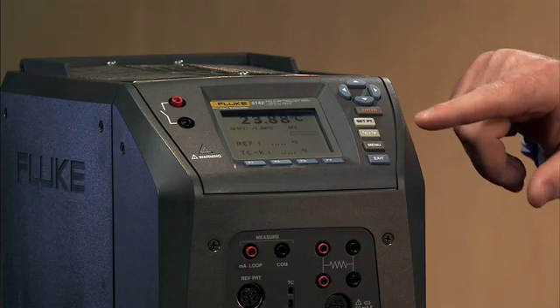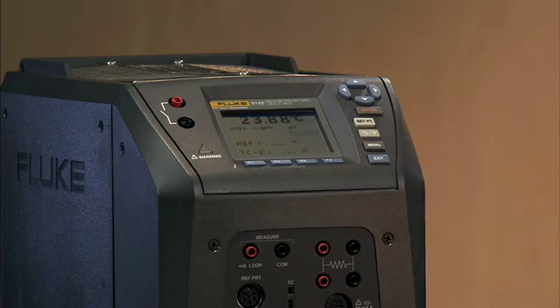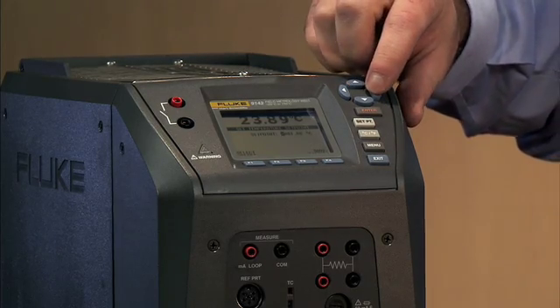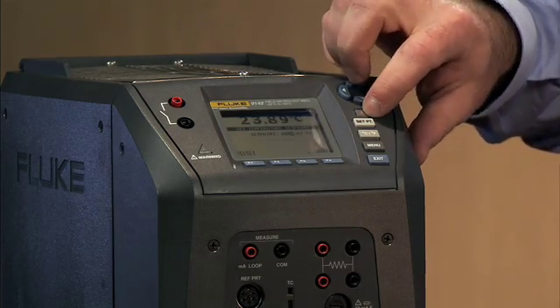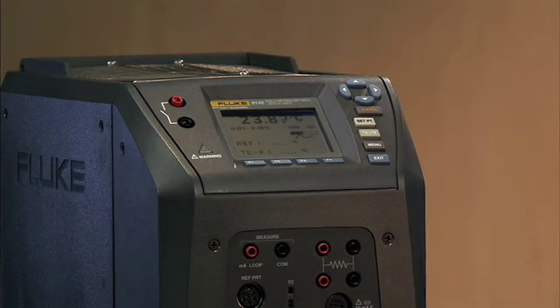As you see on this front panel, we have the set point temperature — we've dedicated a button just to allow you to set the temperature. So you go ahead and press that, press enter, and then you enter the desired temperature that you want. In this case, let's go to zero degrees Celsius, as that's a common temperature for us. Press enter to enable the controls, and now we're going to temperature.